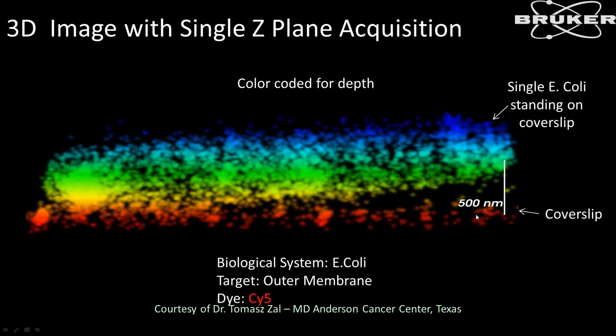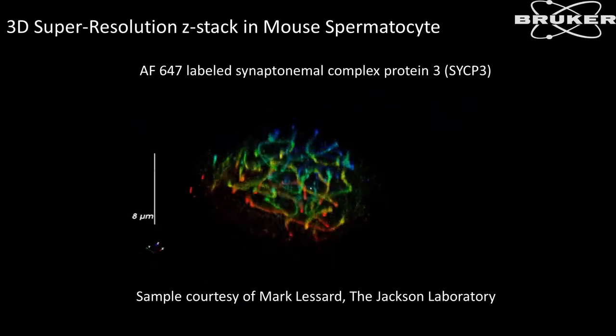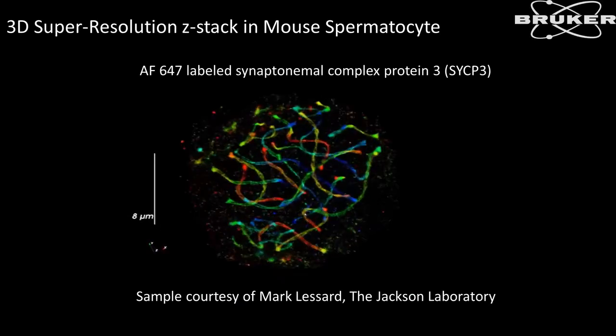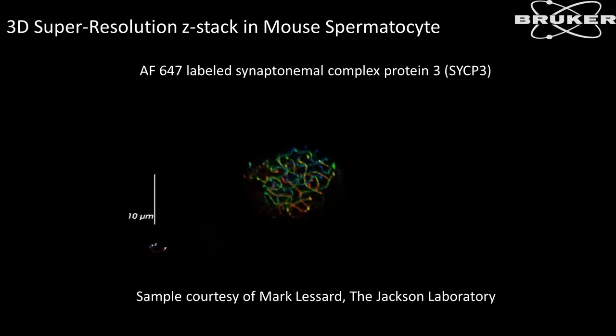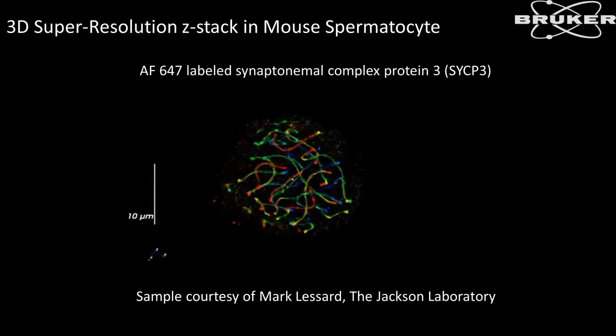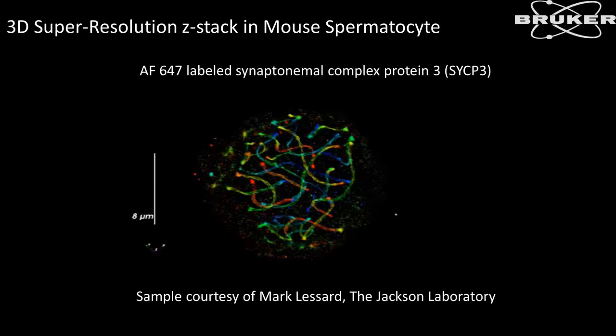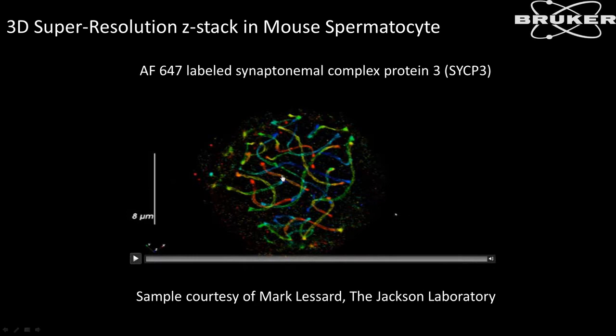Another example of 3D imaging involves Z-stacks. We acquire that one-micron volume with each acquisition, but we can also move the Z-motor and acquire a series of those volumes to get an even thicker Z-range acquisition. This was the case with a mouse spermatocyte, where the full Z-range was a little over eight microns.